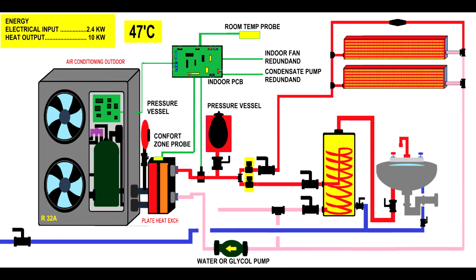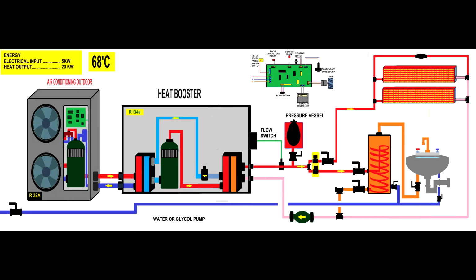Later, I had the courage to build a little bit bigger system, and I cut the pipes from my boilers and I attached the heat pump. So the only thing I had to do was to extend the pipe. You see the red and this little pink pipe, and to connect the plate heat exchanger, which is near the outdoor. And again, I saved the printed circuit board from the indoor, and that gives me full control of the outdoor. And I built my system, and I managed to get out 47 degrees Celsius with only 2.4 kilowatts. I managed to get 10 kilowatts.